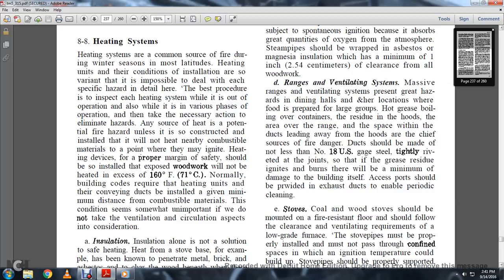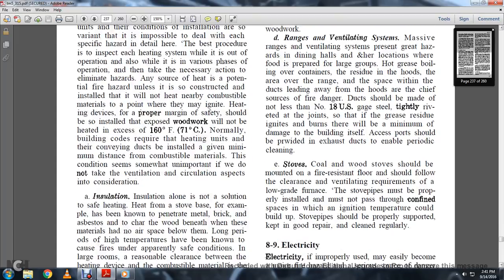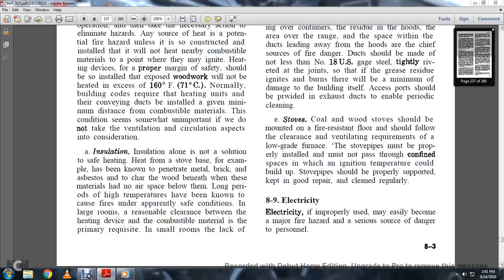Normally, building codes require the heating units and conveying ducts to be installed at a given minimum distance from combustible materials. This condition seems somewhat unimportant if we do not take the ventilation and circulation aspect into consideration. Insulation alone is not a solution to safe heating. Heat from a stove base, for example, is known to penetrate through metal, brick, or asbestos to the wood beneath, when these materials have no airspace between them. Long periods of high temperatures have been known to cause fire. Apparently safe conditions in large rooms may not hold in small rooms, where reasonable clearance between the heating device and combustible material is primarily required.